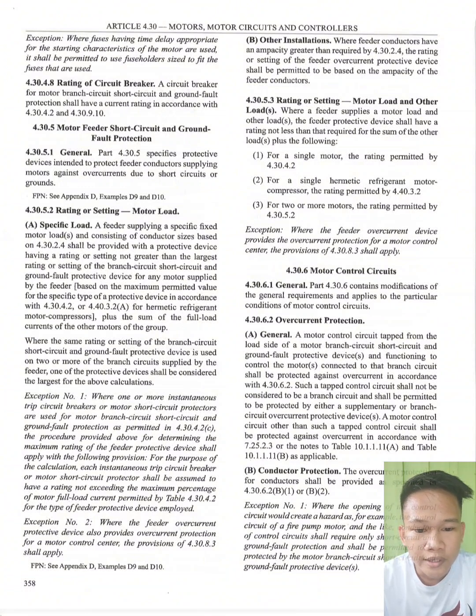Next is rating or setting, motor load. First, specific load. A feeder supplying a specific fixed motor load and consisting of conductor sizes based on 4.30.2.4 shall be provided with a protective device having a rating or setting not greater than the largest rating or setting of the branch circuit, short circuit, and ground fault protective device for any motor supplied by the feeder, based on the maximum permitted value for the specific type of protective device in accordance with 4.30.4.2 or 4.40.3.2(A) for hermetic refrigerant motor compressors, plus the sum of the full load currents of the other motors of the group.